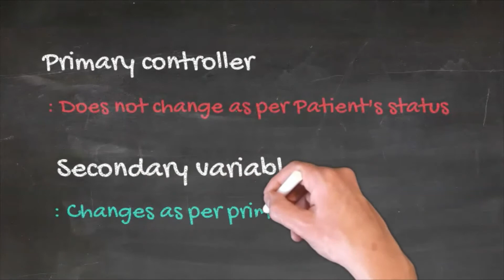Variables can be categorized into two types: primary controller and secondary variables. As the name suggests, the primary controller does not change as per the patient status, whereas the secondary variable changes as per the primary parameter and the patient status. The main role of the primary parameter is to deliver tidal volume to the patient.